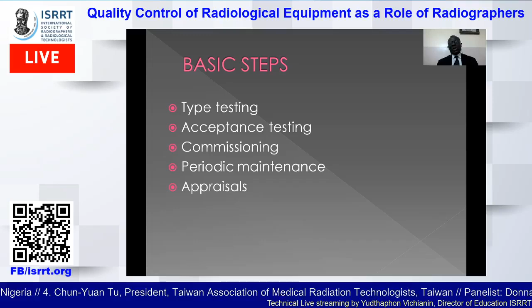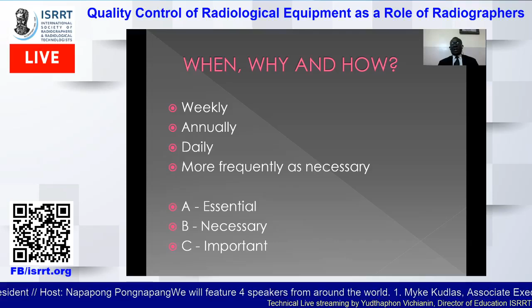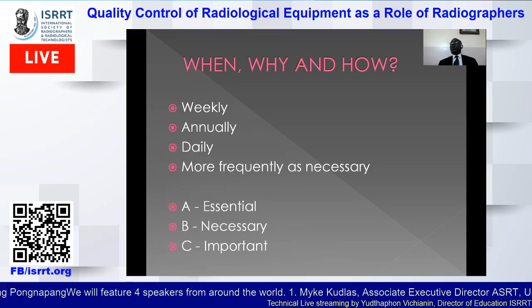The basic tests are type testing, acceptance testing, commissioning, periodic maintenance, and appraisals. The quality control team in every hospital setting should include the hospital management, the radiographers, the medical physicists, the radiologists, and of course, the technicians. Quality control procedures are carried out on a daily, weekly, or annual basis, as the case may be. Sometimes it could be a little more frequent depending on the status of the equipment, for example if it has just gone through repairs, and the quality control services are considered essential.